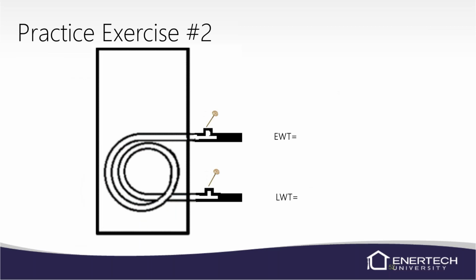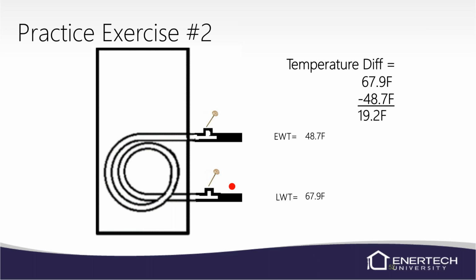Go ahead and take your entering water temperature. 48.7 in and 67.9 out. So we got a 19.2 degree temperature difference. That pretty much tells us, if you didn't already know, that this is probably on an open loop system, or you've got a pump that's bad or something. You're not moving enough water flow. It ought to make you start thinking about things. Maybe you already knew it was an open loop, so you already knew that it should be that high temperature difference. But if not, that number should make you think.